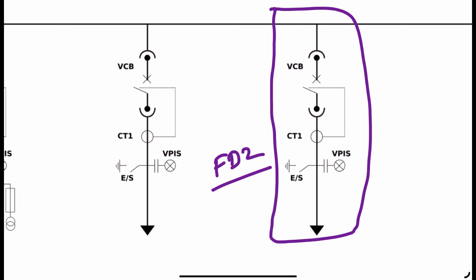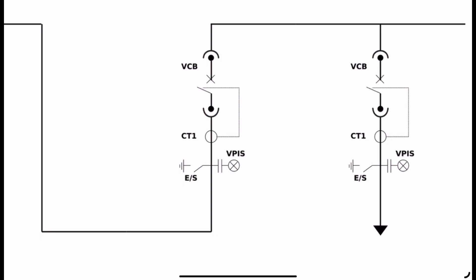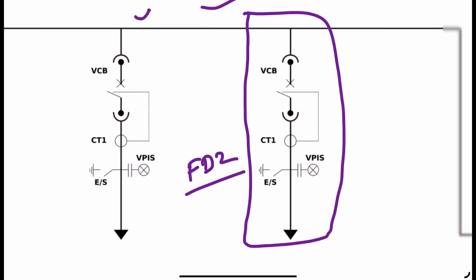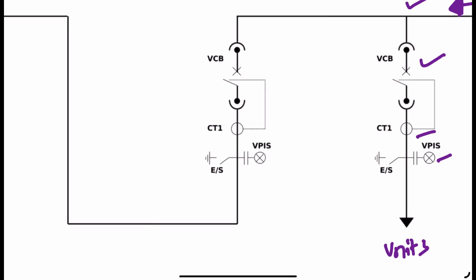Now remember I mentioned I want supply redundancy as well — that problem has not been solved yet. For this, we want one more supply line or feeder coming in. Imagine a different feeder coming from a different substation with its own incomer panel, feeding unit three. These two feeders are from different sources, so if one feeder fails, one unit is still running — but this still does not fully solve the supply redundancy requirement.